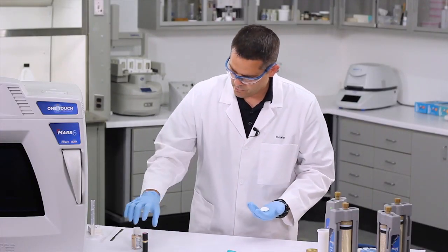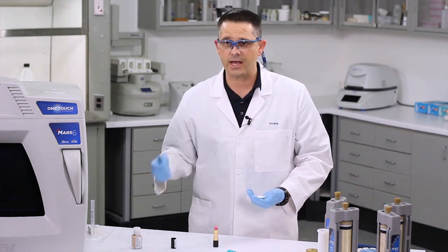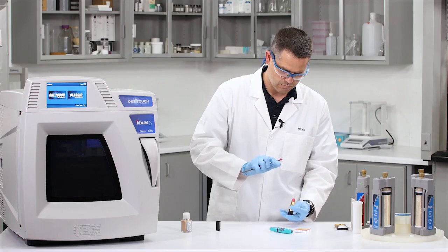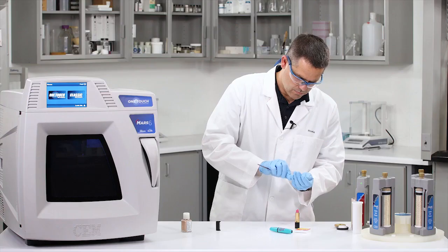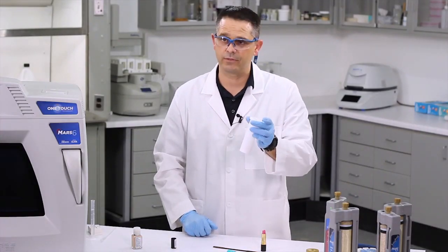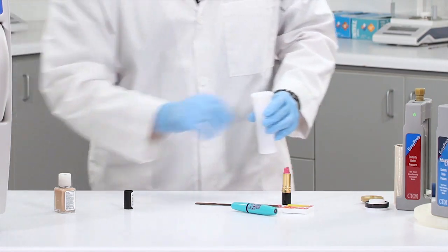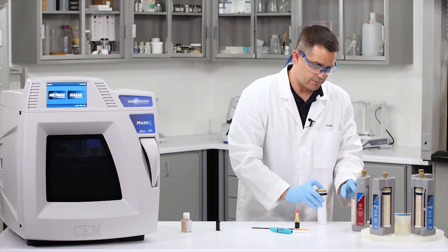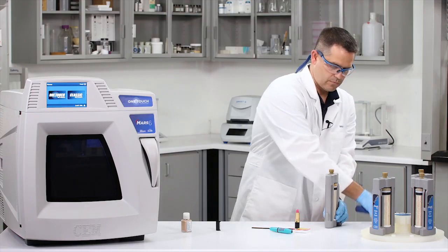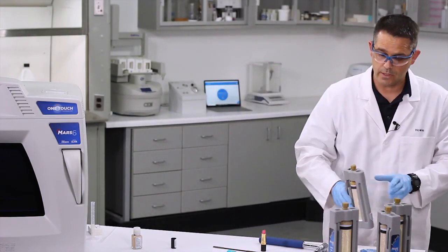Here is our filter paper and we're going to take our lipstick sample. Lucky for me, this scale is NIST traceable, so I'm going to get about a half gram of sample. Place it onto our filter, give it a little fold, and now I'm going to drop it all the way safely to the bottom of the liner. Here's my 10 mLs of nitric acid. Now we're going to be ready to seal this vessel and go ahead and load it onto our turntable, and off to the microwave we will go.